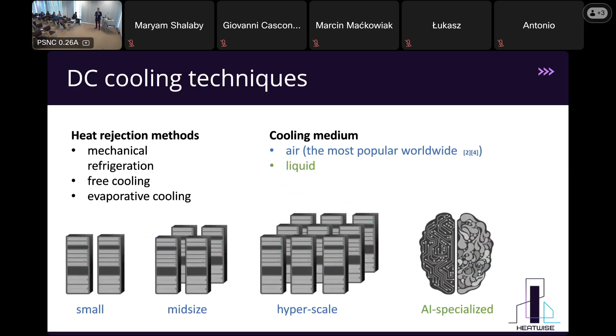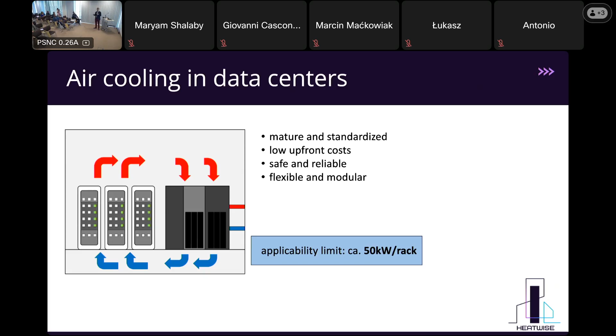So what are the advantages of air cooling? This is a mature solution which was used for decades. It can be flexible, it's safe because there is no leakage of fluid which could damage your IT hardware, and it has relatively low upfront cost. However, there is a limitation to the heat it can dissipate. Because of the relatively low specific heat of air, the estimated upper limit of application of air cooling is close to 50 kilowatts per rack. Above this value, we need to use liquid cooling to effectively dissipate the heat.